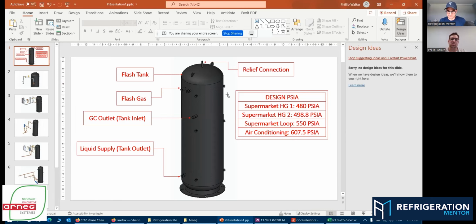That's being controlled. That gas on the top of this flash tank is regulating the pressure in this flash tank. And there's a valve doing so, which we'll get to. So that's why you have 2 inlets here. We're going to have one connected to a flash gas bypass. We're going to have the other one connected to either a backup emergency unit, flash gas subcooling, which we do, or hot gas defrost. Okay, which I hope we'll get time.